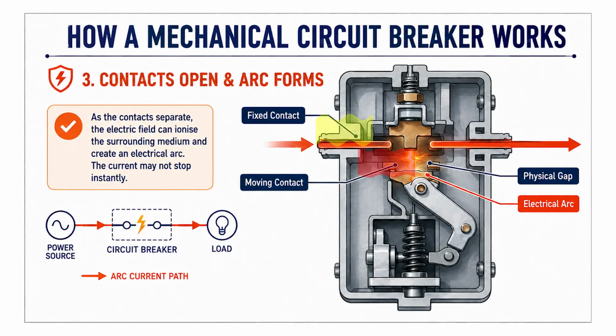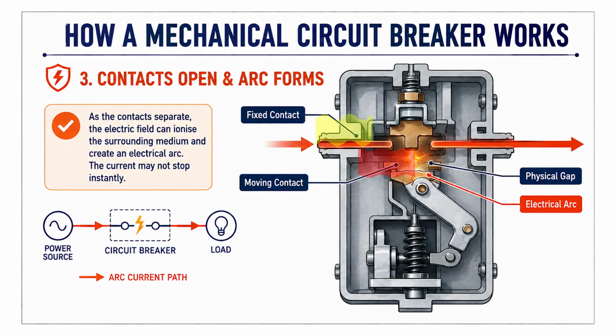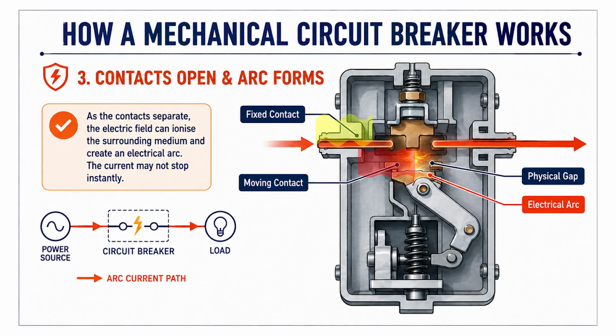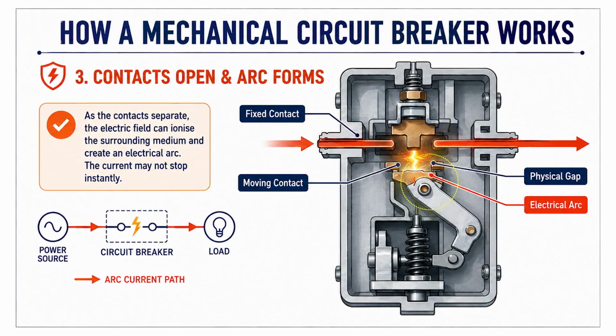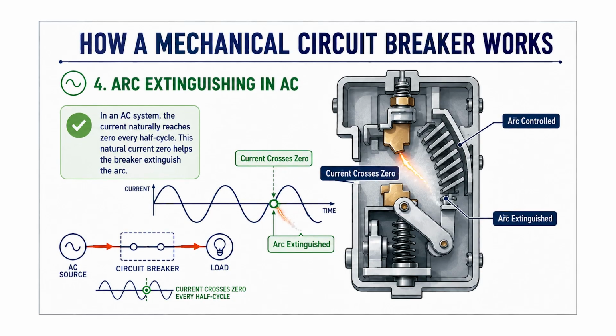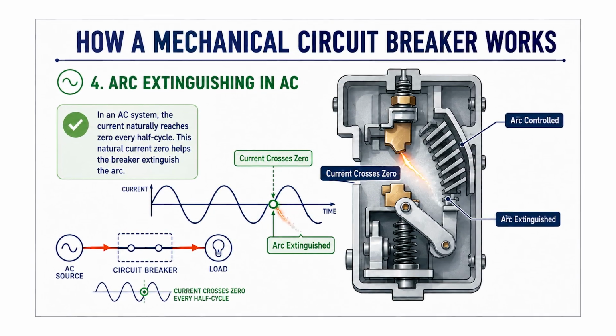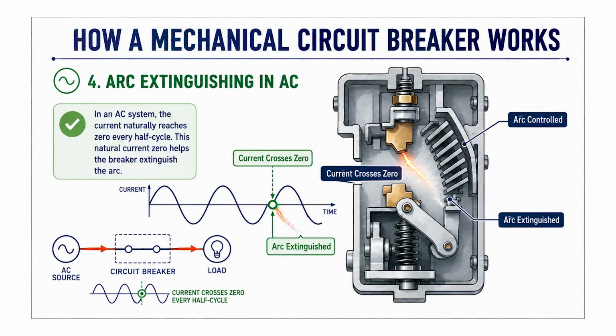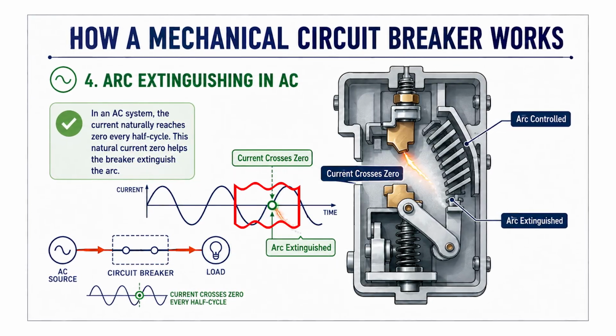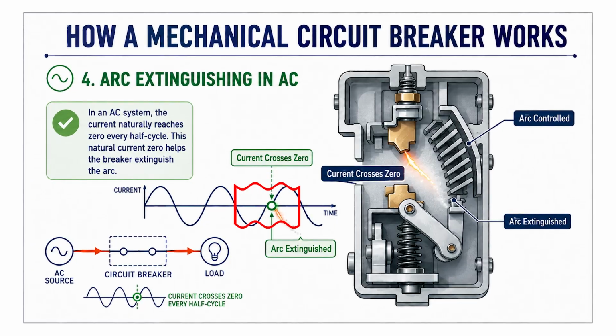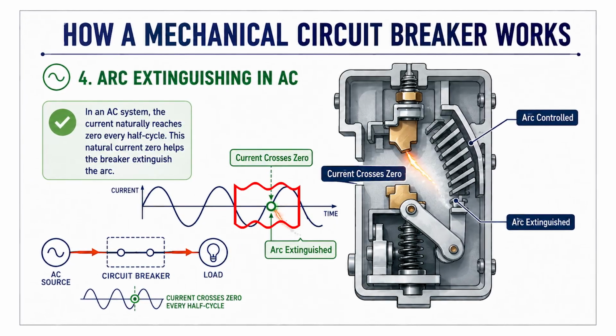As this gap increases, the electric field between these contacts can ionize the atmosphere around it and create an electric arc. The breaker must control, cool, and finally extinguish this arc before the current is completely interrupted. In traditional AC distribution networks, with AC mechanical circuit breakers, the AC current naturally crosses zero at every positive and negative cycle. So this natural current zero helps the breaker extinguish the arc. But in a DC system, there is no such thing. There is no periodic natural current zero in DC systems.